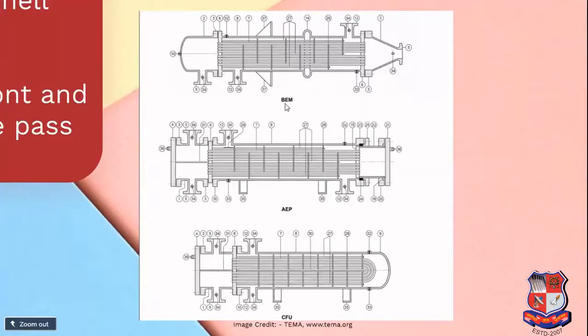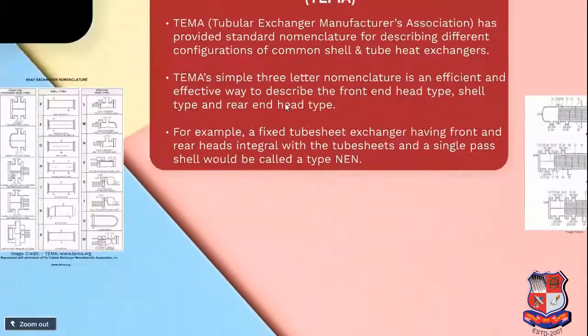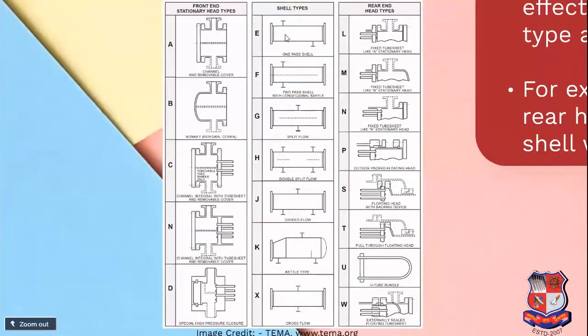Okay. Now take a look at the TEMA table. Here, B stands for front end stationary head, which is a bonnet integral cover type, which is similar to the diagram. The second one was E. E stands for shell side. It means that the shell has one pass. Last one was M. Here M says that fixed tube sheet like B stationary head. So your tube sheet is fixed over here. This is a tube sheet at which the tubes are attached, and the head is stationary.